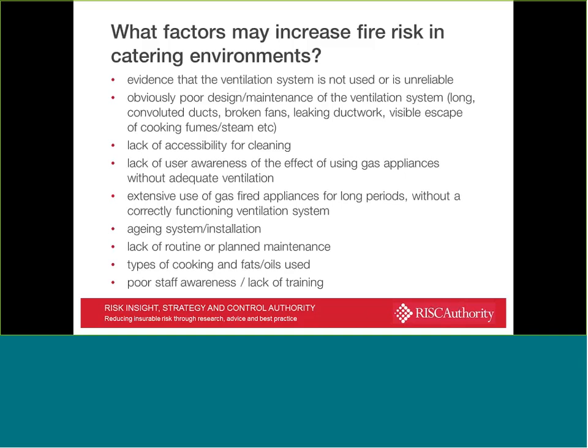Lack of accessibility for cleaning is very common and one of the most significant reasons why ductwork may not be effectively cleaned and may support combustion. Lack of user awareness of the effect of using gas appliances without adequate ventilation. Often that's not clearly established, which may create some form of flammable environment. The extensive use of gas-fired appliances for long periods without a ventilation system, or an aging system or installation that's clearly no longer fit for purpose. There may be a lack of routine or planned maintenance, which again would cause concern.